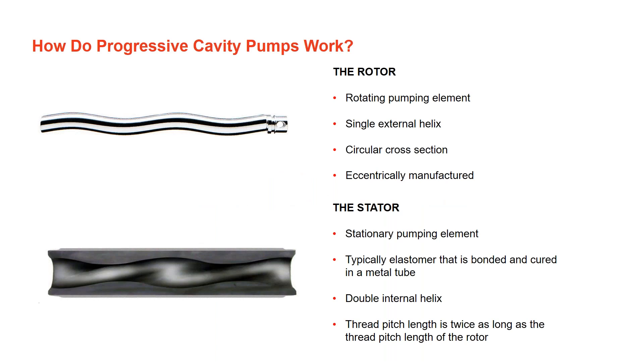How does a progressive cavity pump work? You have your rotor — also called the worm — a single helix manufactured in various ways by different companies. Then you have the stator, which is the main wear element and takes the greatest beating. If the stator is compromised, damaged, or starts breaking apart, the pump won't operate correctly. The stator is a double helix and can even be flipped or installed upside down — it doesn't matter, the rotor will always fit inside it. The key is maintaining that tight compression fit and proper seal lines.